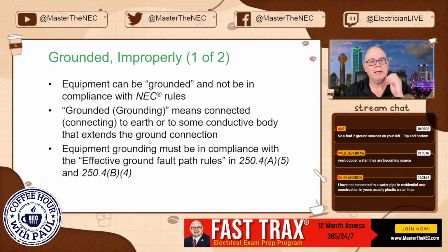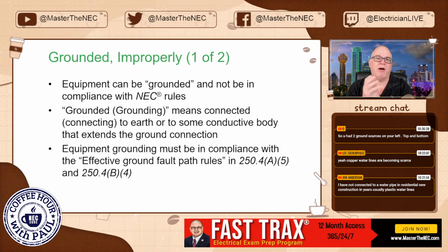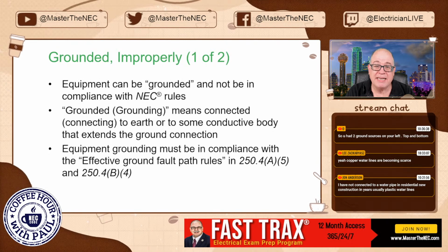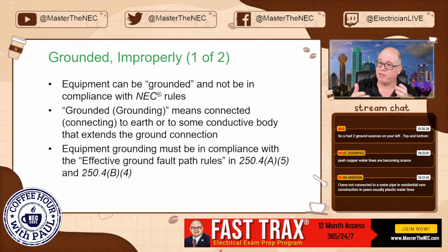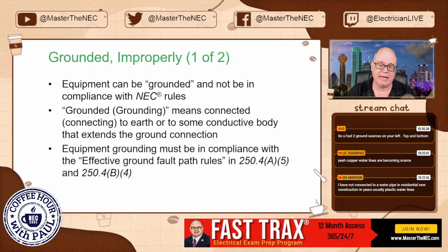All right. Grounded improperly. Equipment can be grounded and not be compliant with the NEC. So this happens a lot. A good example of this is a light pole out on a parking lot.